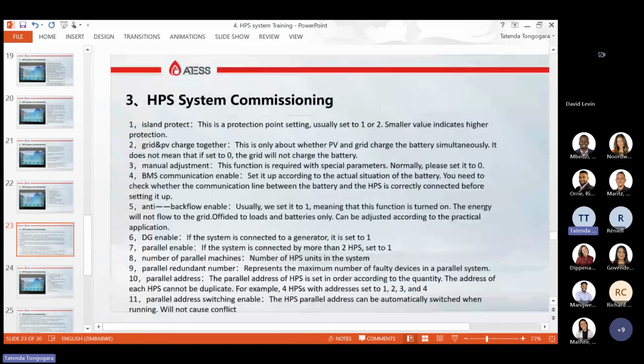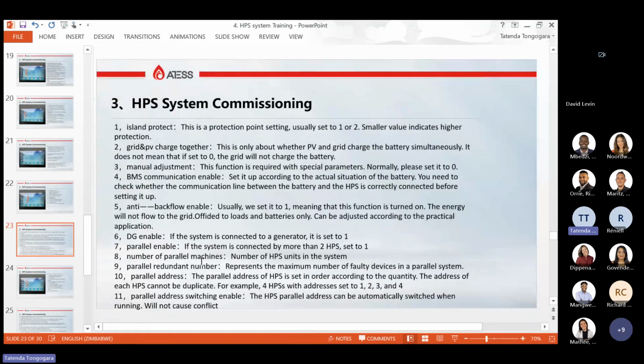So these are the description of the settings that I was talking about. You can go through these when you are doing your commissioning or before you go to site. So this is anti-backflow enable. On some inverters, it's written anti-reflux. Usually we set it to 1, meaning that the function is turned on and the energy will not flow to the grid. If you set it to 1, there is no export to the grid. If you set it to 0, you can export to grid.